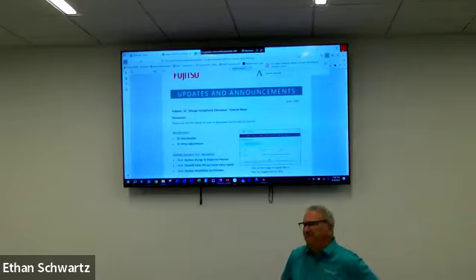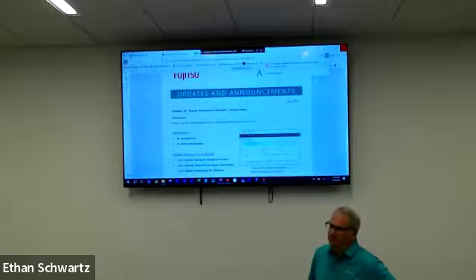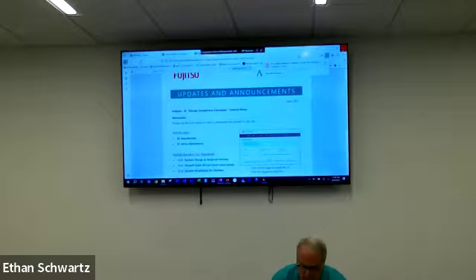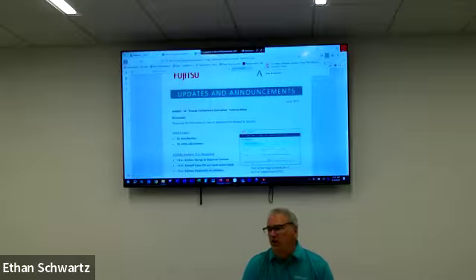So on being compliant, an 8 series R32 multi-port, like a 3-ton multi-port, is not compliant right out of the box. Yes, you're going to have to know what room size you're putting the equipment in, what the square footage is, and what the mounting height of the unit is. Then find out if it's going to need a leak detection sensor or refrigerant detection sensor. LDS and RDS are kind of interchangeable, but one is more the refrigerant detection that would shut off that system, and that's not built in, except in our ducted units.